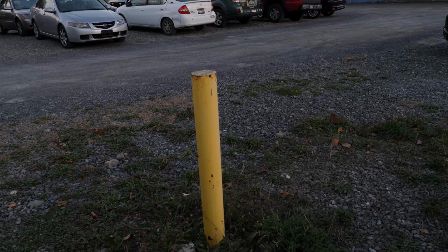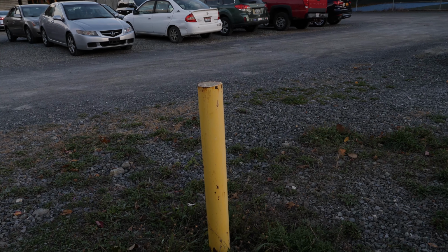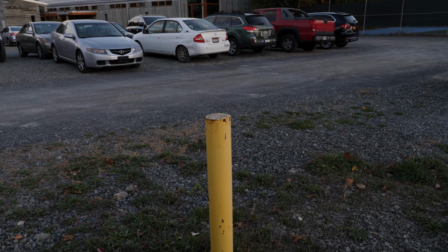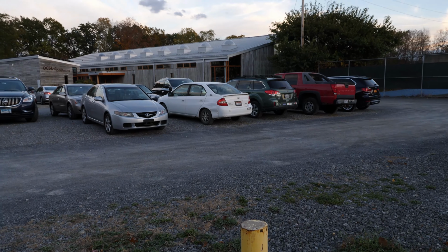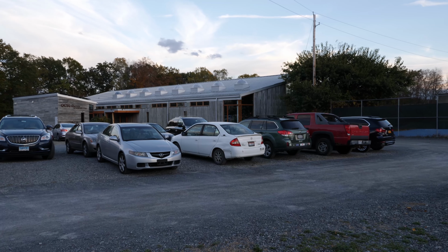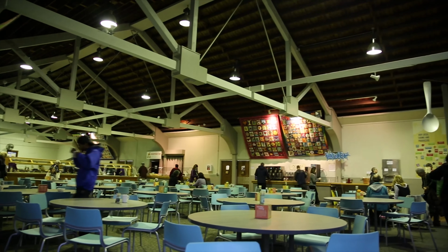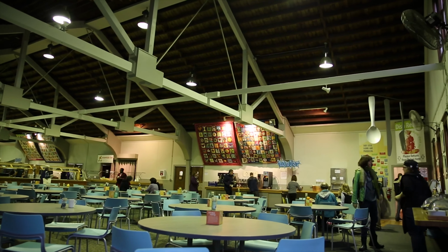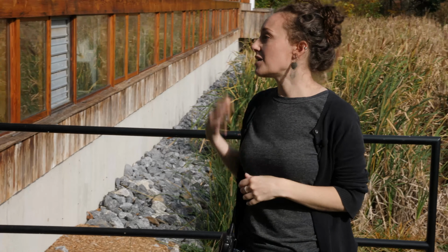Those are the equalization tanks. So we have that water flowing in so that we're able to catch the peak flows. In the mornings and the evenings, everybody is showering at the same time, so you have a huge load of water that's coming down here. We'd need a much bigger system if we were just processing that as it came in. So they created that to be able to equalize the flow over the course of the day.